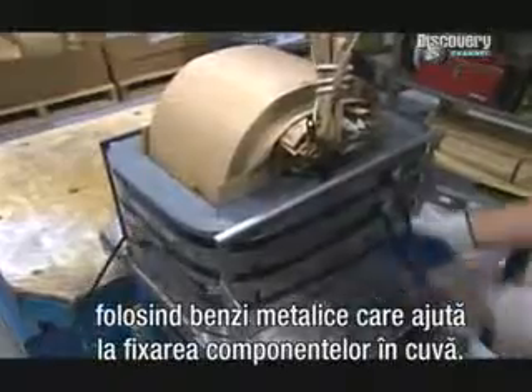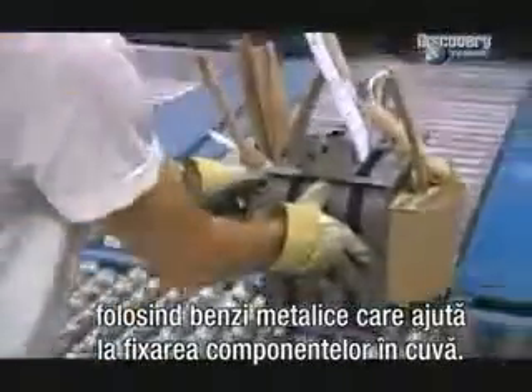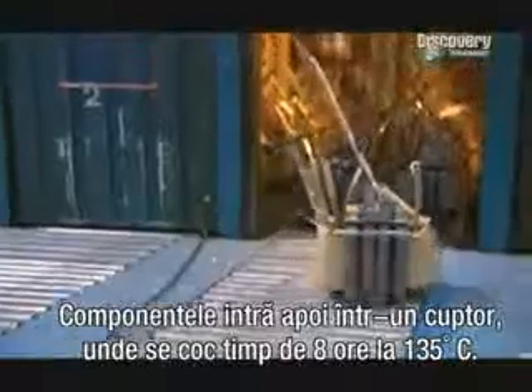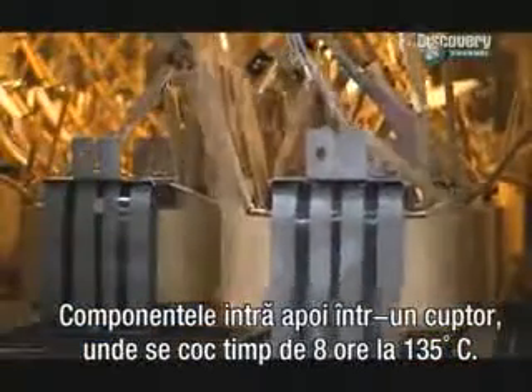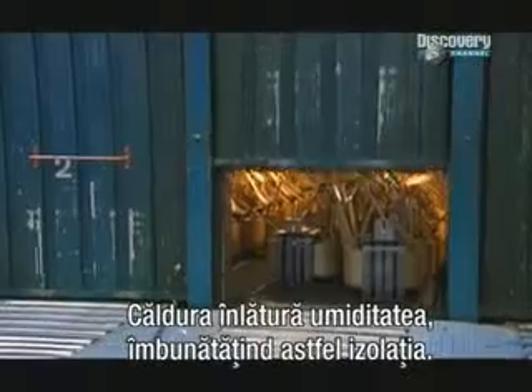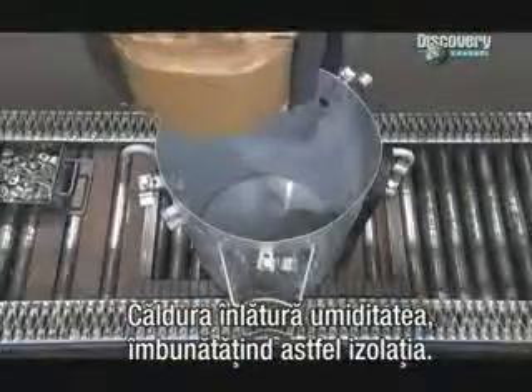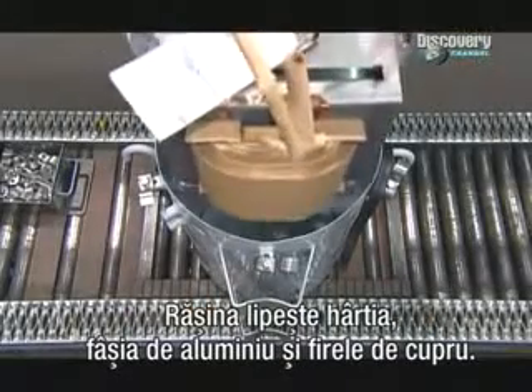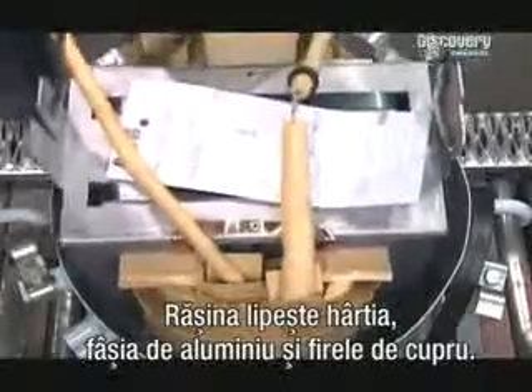A worker secures the coil and cores tightly together with metal strapping, which will help fix the assembly in the tank, then sends them to an oven, where they'll bake for 8 hours at 135 degrees Celsius. The heat removes any traces of humidity to improve the insulation. The epoxy glue has fused the paper, the aluminium strip, and the copper wires.